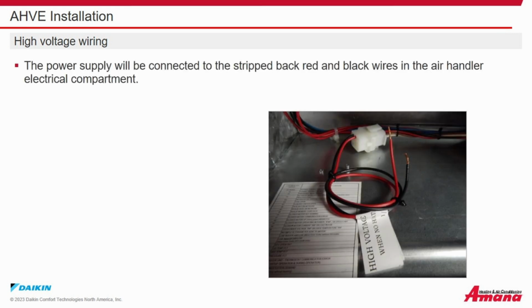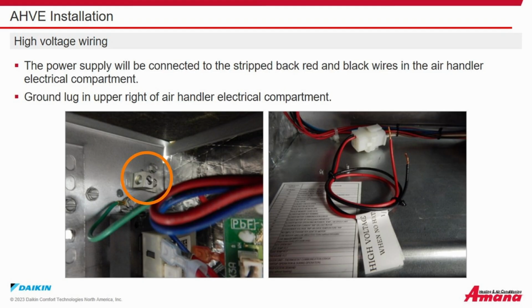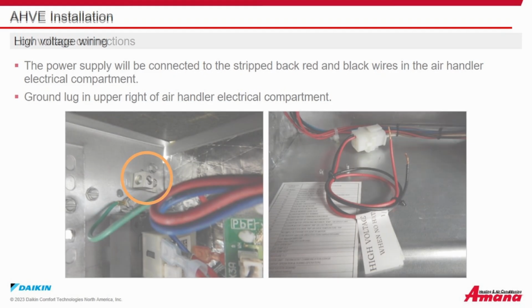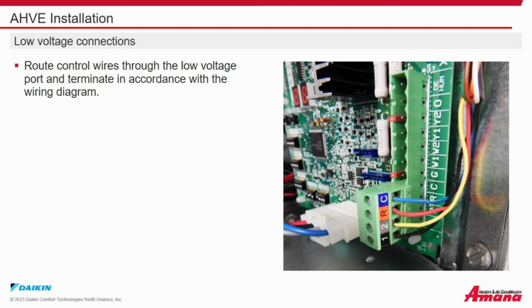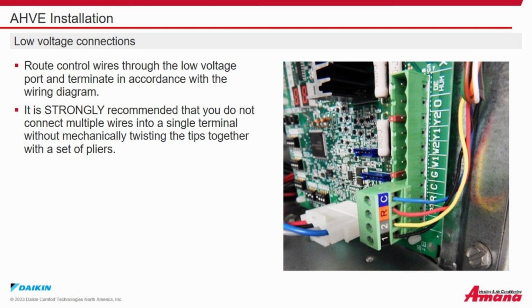High voltage wiring. The power supply will be connected to the stripped back red and black wires in the air handler electrical compartment. The ground lug is located in the upper right corner of the air handler electrical compartment. Low voltage connections. Route the control wires through the low voltage port and terminate in accordance with the wiring diagram. It is strongly recommended that you do not connect multiple wires into a single terminal without mechanically twisting the tips together with a set of pliers. Minimum 18 gauge wire.